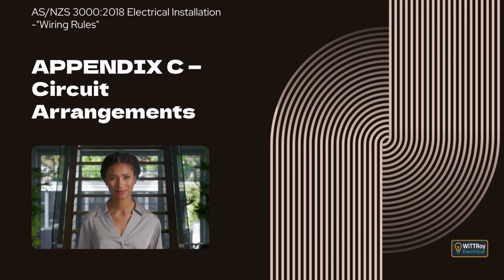Clause C2.5.3 Domestic cooking appliances. This clause explains that the maximum demand for a final subcircuit supplying domestic cooking appliances may be less than the full connected load. Assessed maximum demand values are applied based on the total connected energy rating of the appliances. Clause C2.5.4 Interlocked equipment. This clause explains that where multiple items of equipment are connected to the same final subcircuit but are interlocked so that only a limited number can operate at one time, the maximum demand is assessed from the combination that produces the highest simultaneous load.